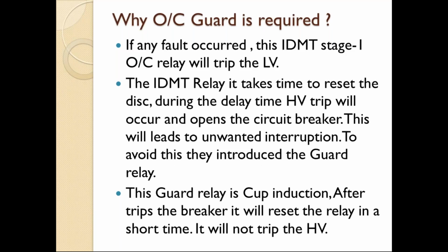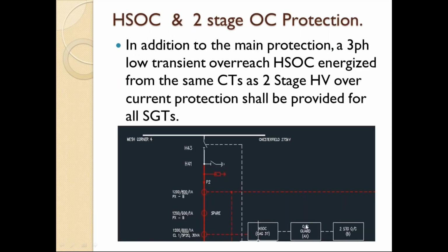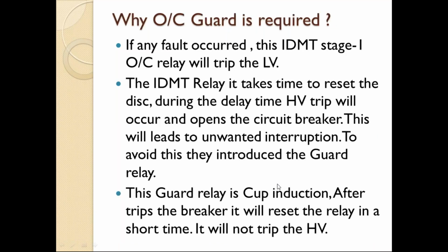And that's why we are going for this Guard relay. It is a cup induction type relay. So this Guard relay will reduce the time, so that only the LV breaker will trip, and there will not be any HV breaker tripping.